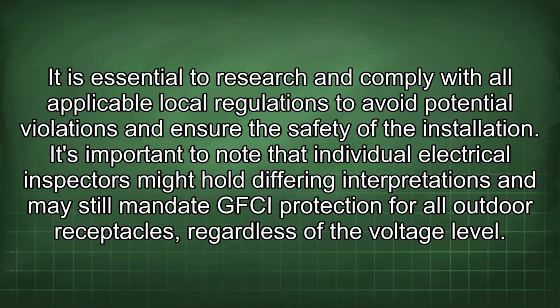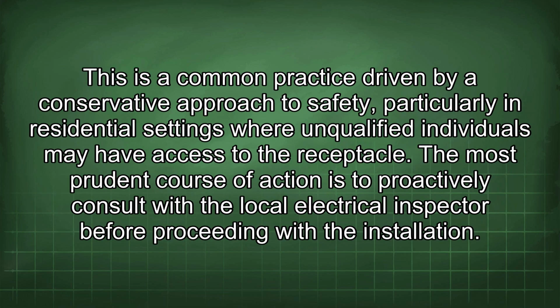It's important to note that individual electrical inspectors might hold differing interpretations and may still mandate GFCI protection for all outdoor receptacles, regardless of the voltage level. This is a common practice driven by a conservative approach to safety, particularly in residential settings where unqualified individuals may have access to the receptacle.